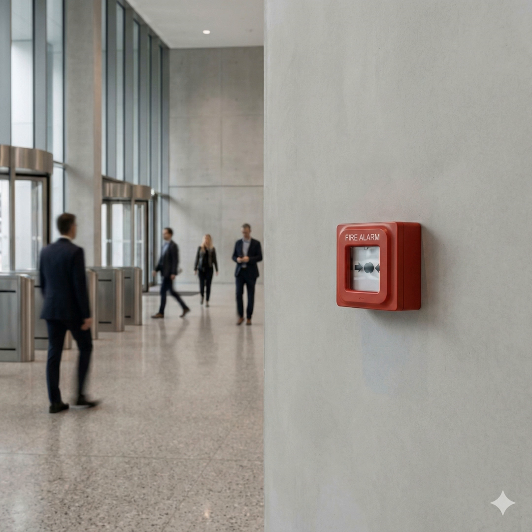2 hours. How do you achieve that in practice? Specialized installation techniques, often using mineral-insulated or MI cables, which are inherently fire-rated, or dedicated 2-hour fire-rated raceways. It's applying a physical security layer directly to the communication network.